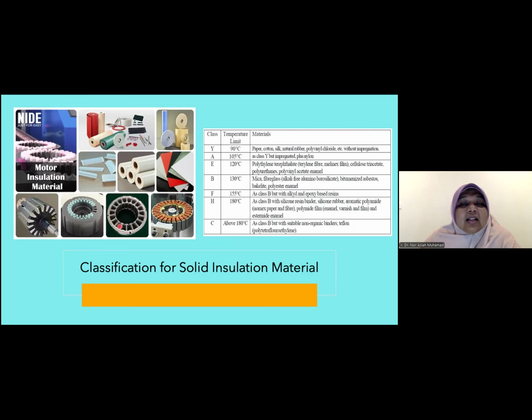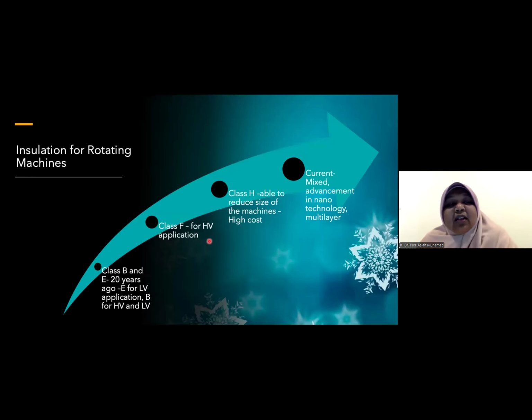So then we cannot use oil because it's a rotating machine. So we use solid material. But if the solid material is damaged, we need to replace it. The progression of solid materials has been studied for quite a long time. We had class B and class E 20 years ago, I think now going to 30 years ago. Then they introduced class F for high voltage application. Then they introduced class H to reduce the size of the machine, because if the insulator is big, then the machine is heavy, so it will be costly.